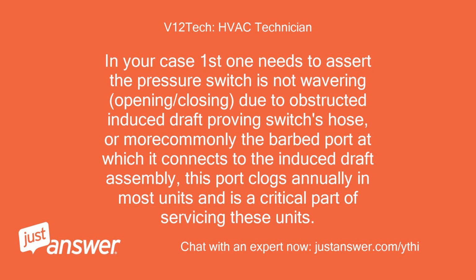In your case, first one needs to assert the pressure switch is not wavering, opening/closing due to an obstructed induced draft proving switch hose, or more commonly the barbed port at which it connects to the induced draft assembly. This port clogs annually in most units and is a critical part of servicing these units.